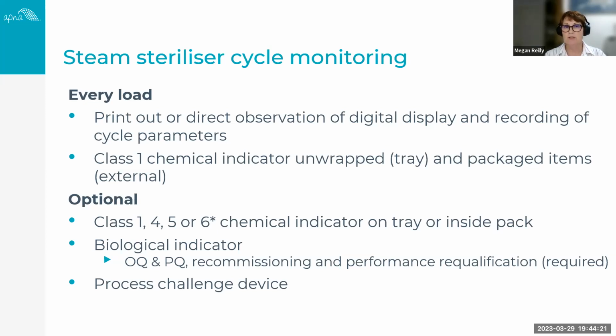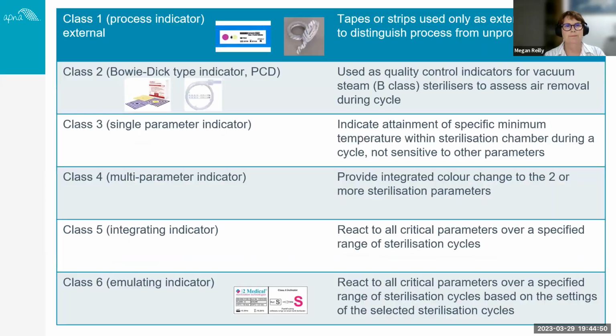Some practices like to do a regular biological indicator. They don't like to wait for once a year when their validation is actually undertaken. And a process challenge device in a class B sterilizer is still optional at this point in time. What a process challenge device is for those hollow items is that it measures that the steam was able to penetrate the most inner part of that hollow item, which is really important if you're using hollow items.